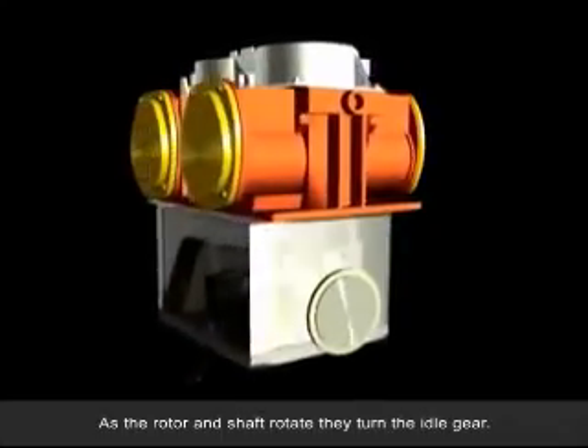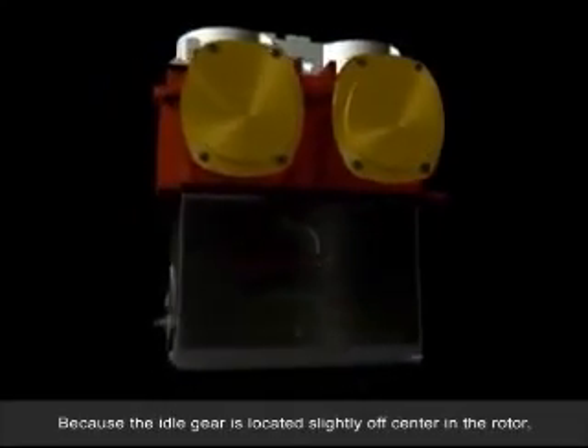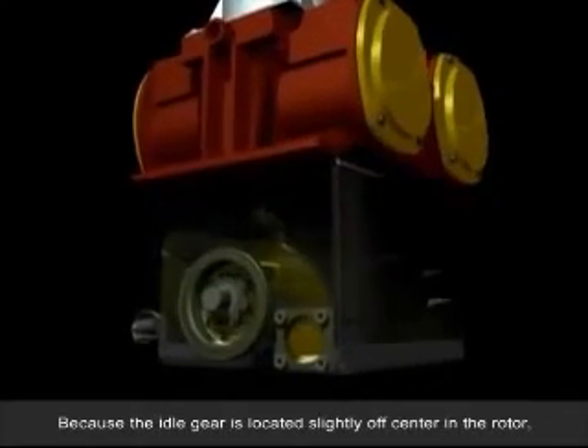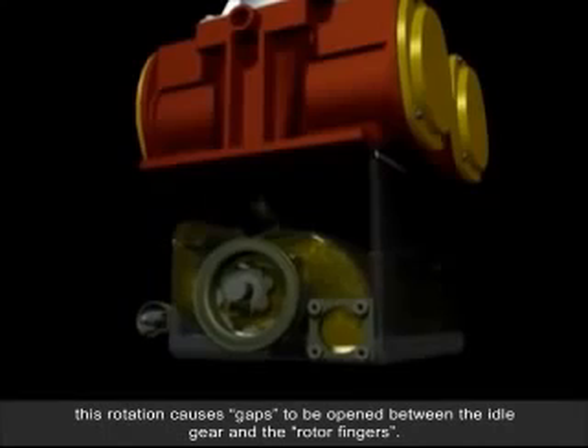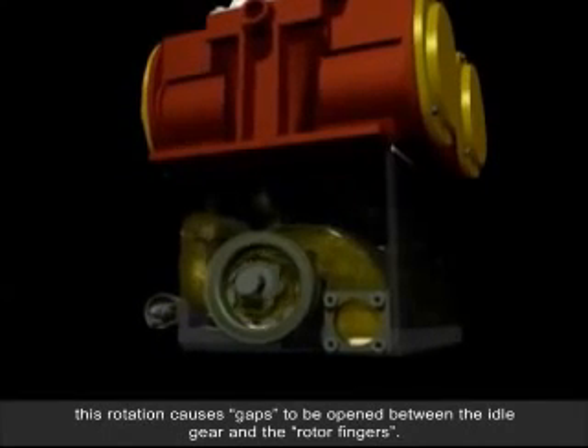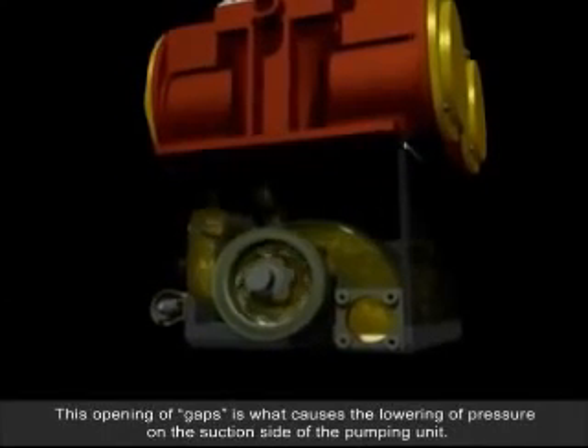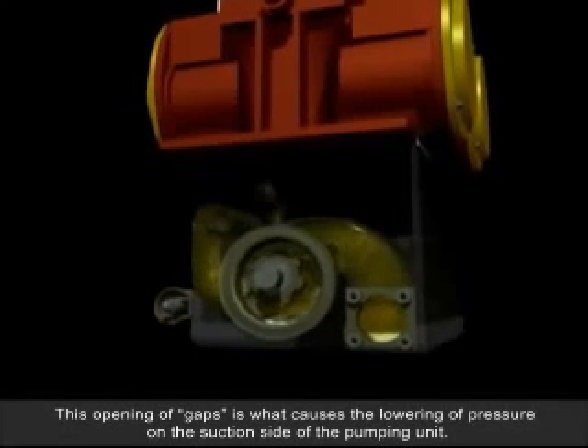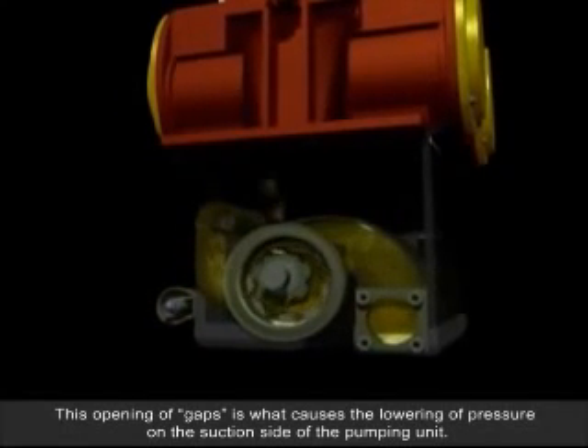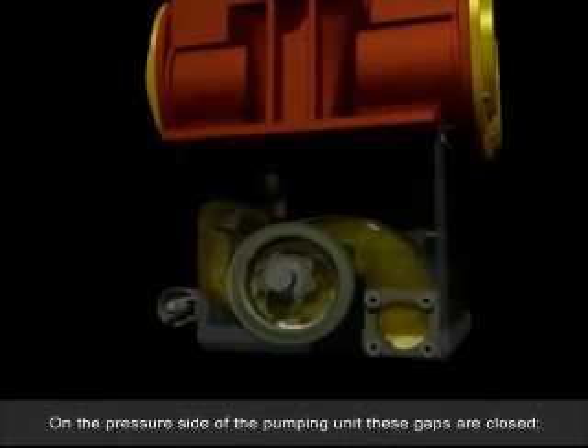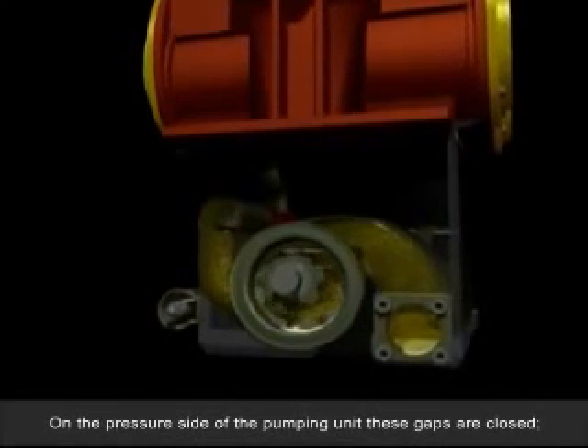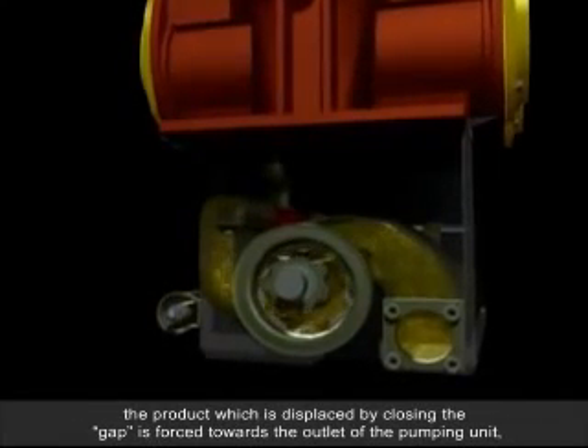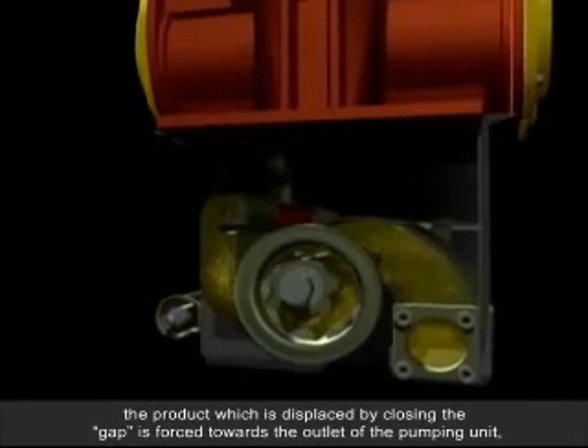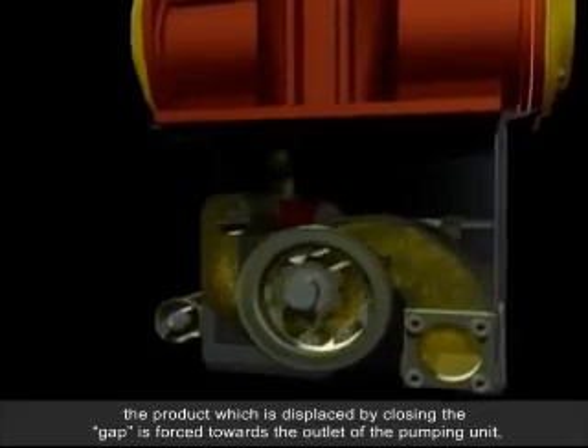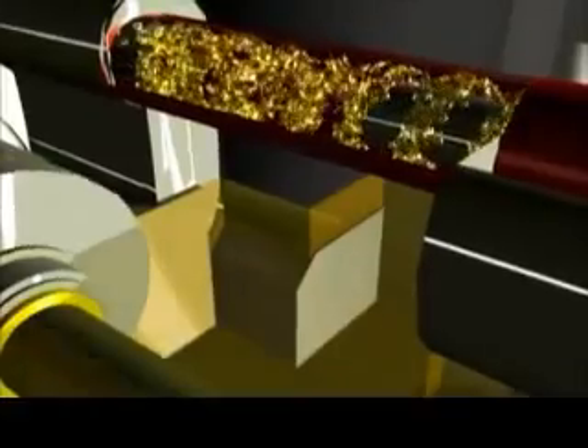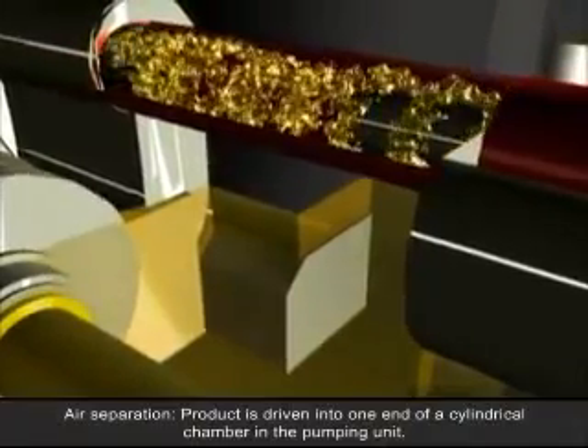As the rotor and shaft rotate, they turn the idle gear. Because the idle gear is located slightly off-center in the rotor, this rotation causes gaps to be opened between the idle gear and the rotor fingers. This opening of gaps is what causes the lowering of pressure on the suction side of the pumping unit. On the pressure side of the pumping unit, these gaps are closed. The product which is displaced by closing the gap is forced towards the outlet of the pumping unit, thus causing an increased pressure.